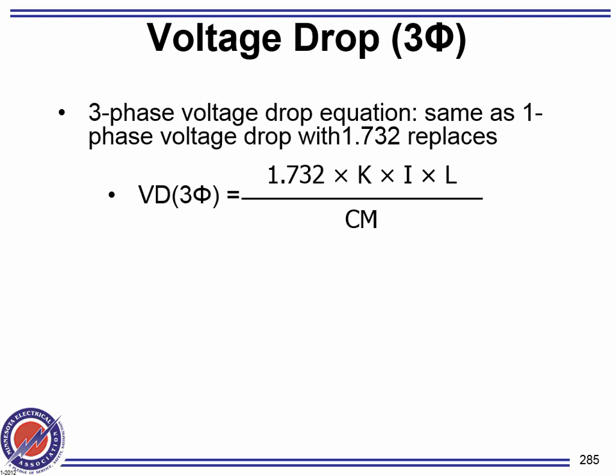Three phase. Here's your formula for three phase, gentlemen. The only difference, anybody can see the difference is what? 1.732. Why 1.732? Because three phase calculates the voltage drop between phase to phase. Single phase calculates the voltage drop between phase and neutral, or phase. Like, what happens if you have a 208 circuit? You have a heater sitting there at 208. 208 single phase. Which formula would you use? Single phase, even if it's 208, right?